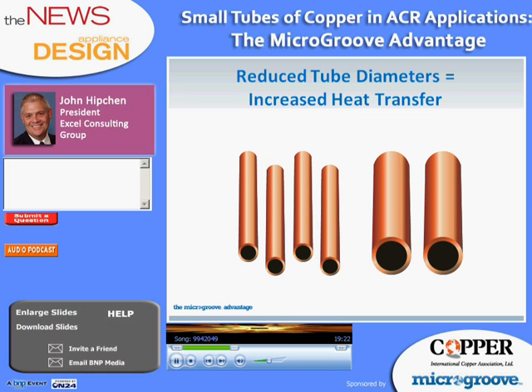And with this increase in heat transfer, we don't need to match the volume or the surface area of the larger tube to get the same amount of cooling. Another benefit that we haven't mentioned yet is that in a smaller diameter tube, we can hold the same pressure as a larger diameter tube, but we can do it with thinner tube walls. So when we reduce tube diameters, we can actually reduce the weight of the materials being used and in turn reduce costs.